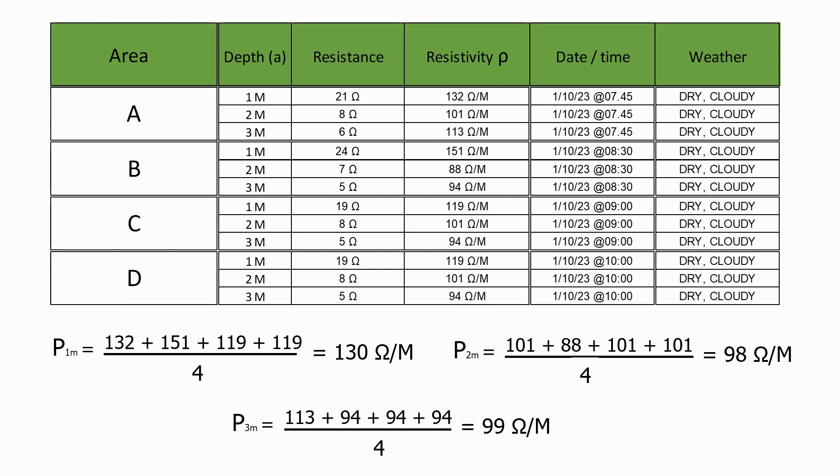As you can see, the soil resistivity tends to reduce as the depth of the soil increases. This effect is quite common and is normally due to the water table, which will sit at a certain depth below ground level. As soon as you get below the water table, the soil will become saturated with water, which will always reduce the value of the soil resistivity.